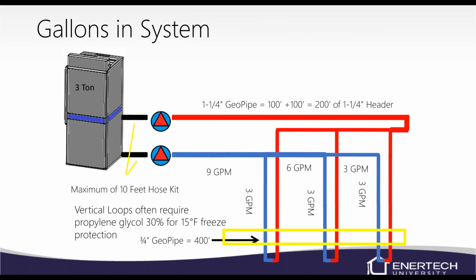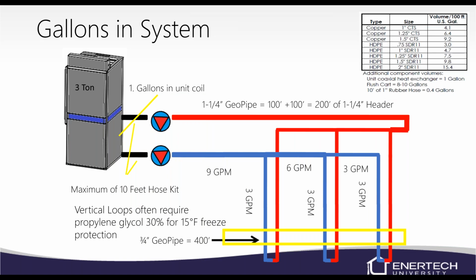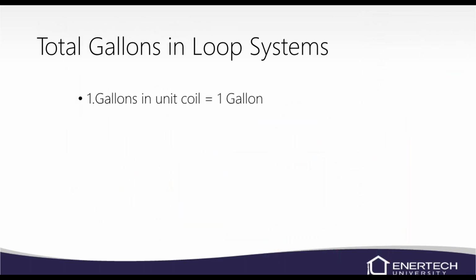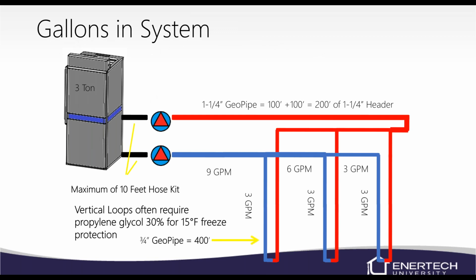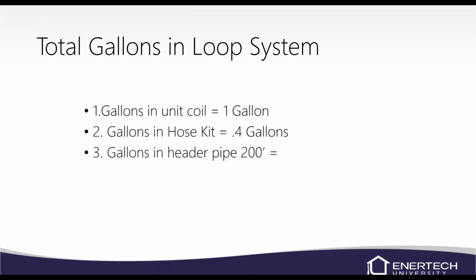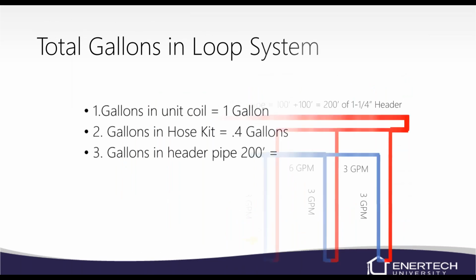Basically, if you've got this system here, you've got 1.25-inch PE pipe, you've got 200 feet in the header. We know we've got 3 vertical loops that are 3/4-inch PE pipe again at 400 feet. So we know what's in the unit, we know what's in the hose kit, we know what's in the flush cart. So if the unit has 1 gallon, the hose kit has 0.4 gallons, and the header pipe is 200 feet of 1.25-inch pipe, we can actually look on that chart.